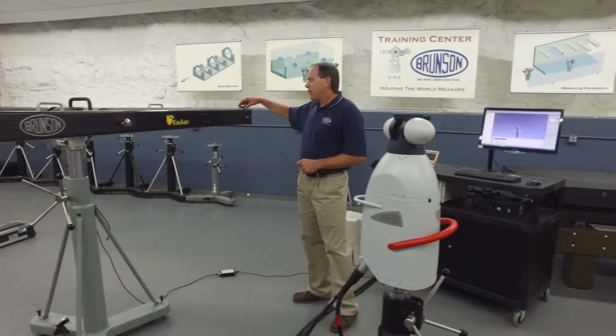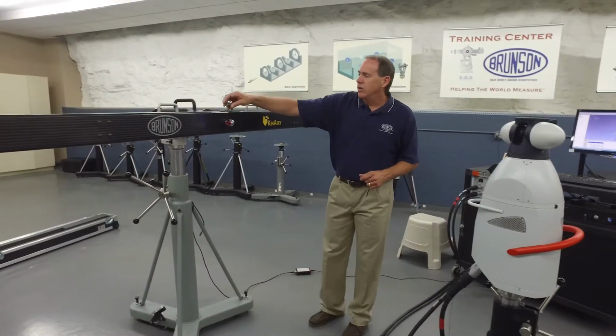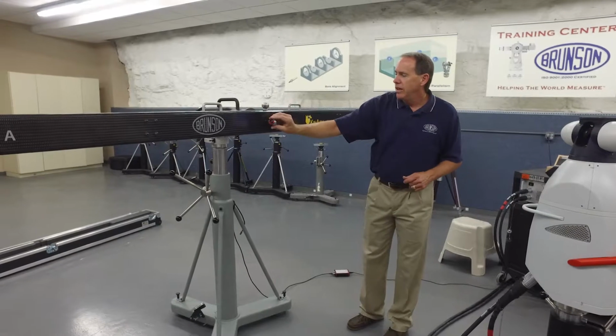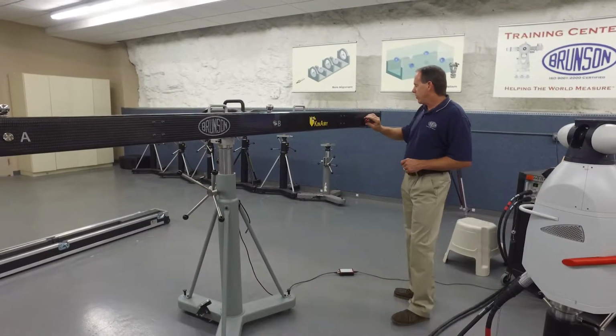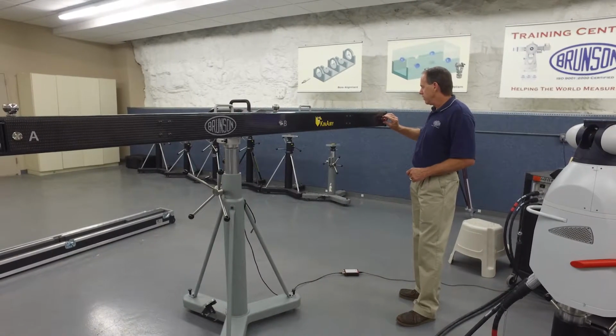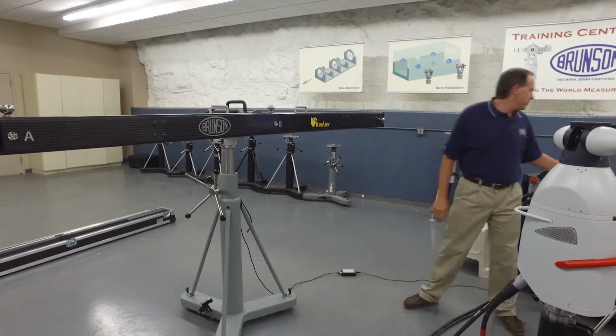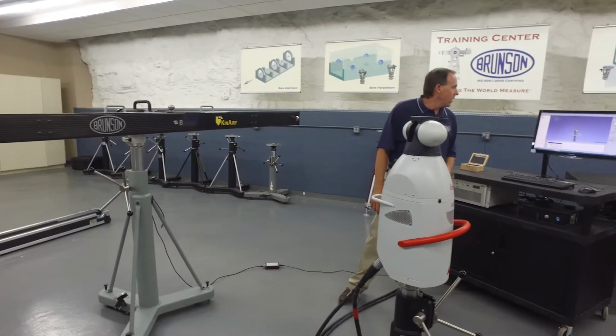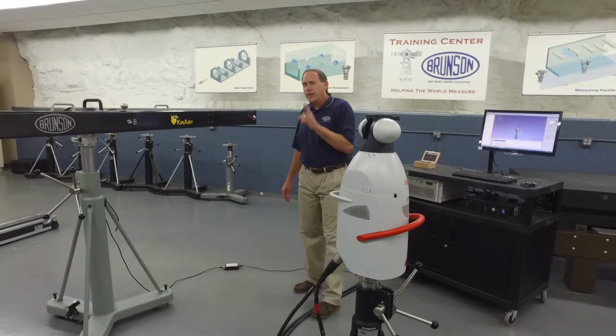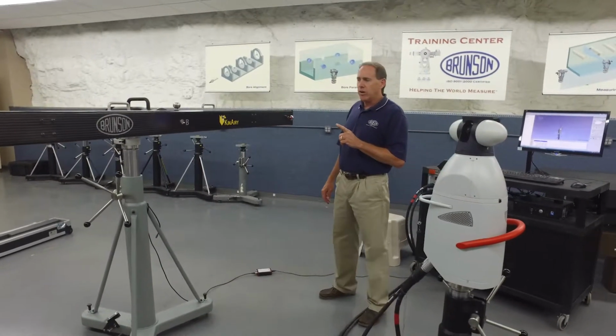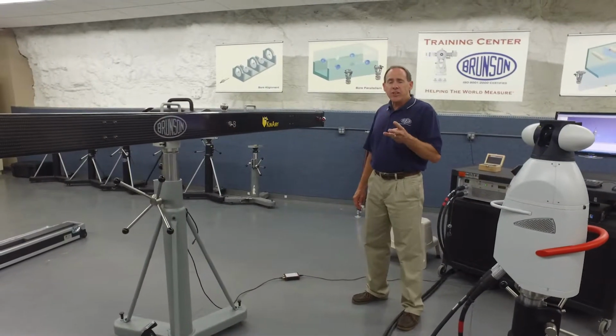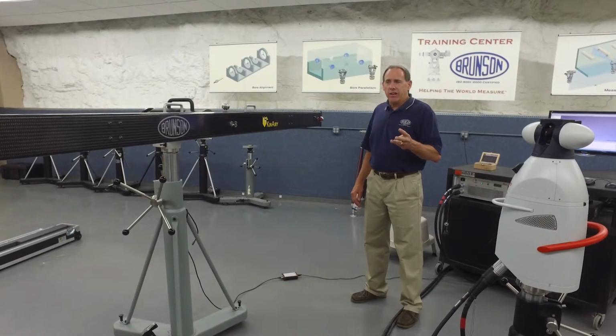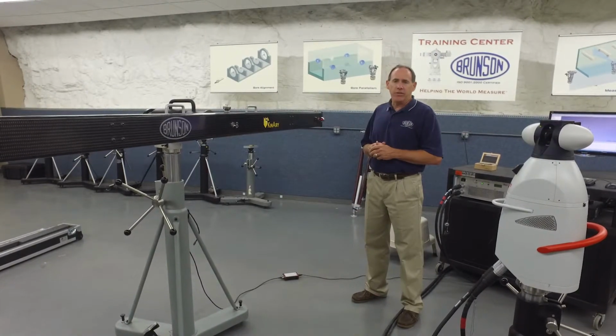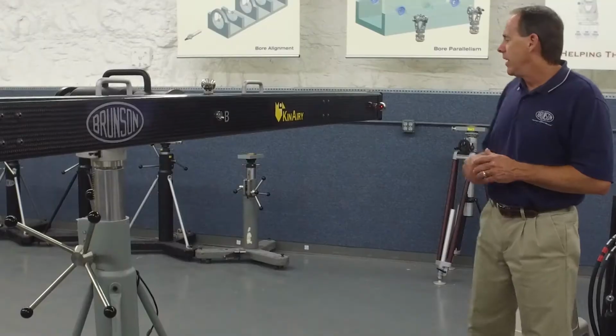So you can see this will become a very repeatable process. We're going to move the counterweight to B as we pull the target back to point C. And let's take our reading. So that constitutes one iteration of the calibration of the bar. We're going to measure this bar 3 times so we can get some average data to better tighten up the calibrated length of the bar.